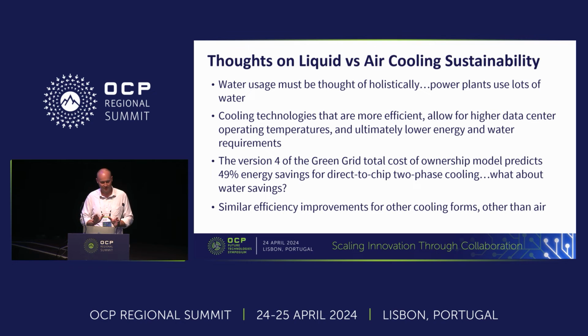I want to make the case that water usage, to be done right, needs to be thought of holistically. Power plants use a lot of water, so anything addressing energy efficiency is ultimately addressing water usage, because you're using less energy, you're saving water at the power plant. From an energy standpoint, I worked on a calculator, version 4 of the Green Grid total cost of ownership model. That model predicted about 49% energy savings with direct-to-chip two-phase cooling.